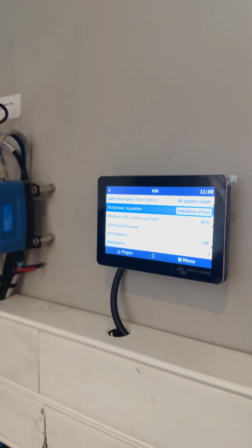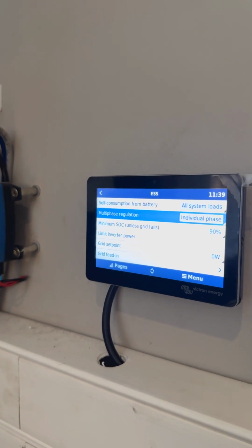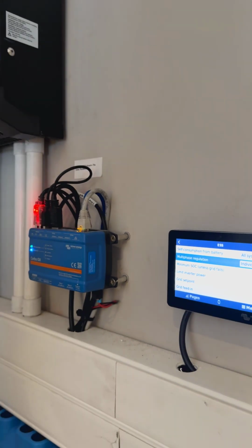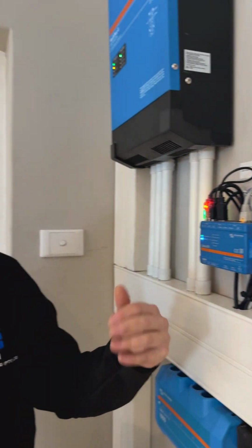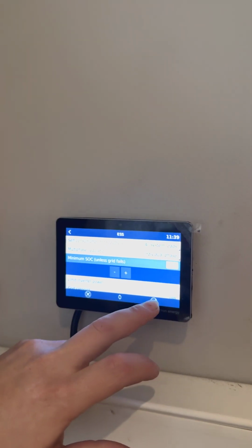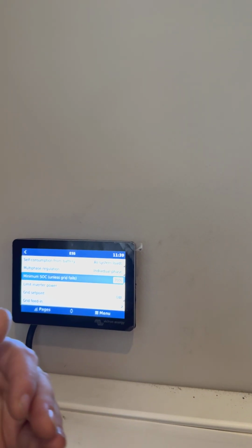This one is quite self-explanatory. Your minimum SOC unless grid fails. SOC stands for state of charge. So if you use the ESS system, you want your battery to drain when there's not enough sun. So in overcast weather or during the night, if you want to save this, ESS is mostly to save from Eskom. So if you want to not use your Eskom or your grid side to feed your loads during the night, you want to save on that, you can set up the ESS and drop it down to a lower percentage, so then it will use 30%.